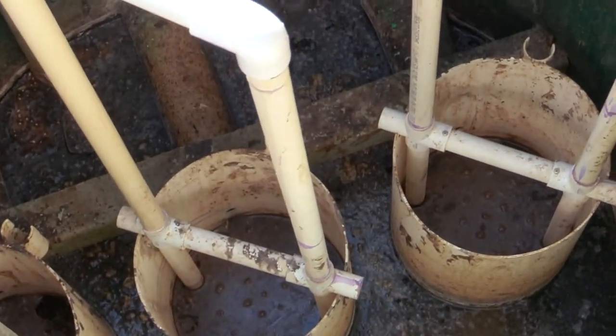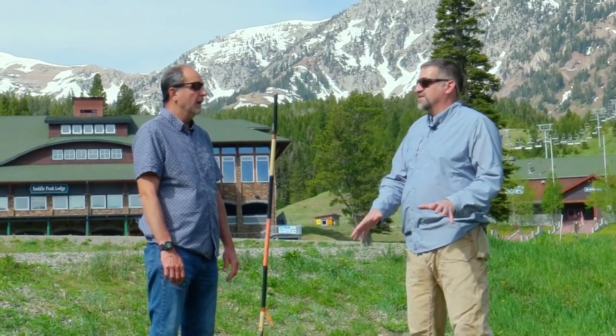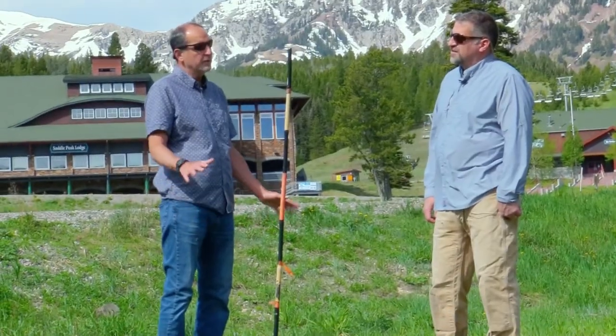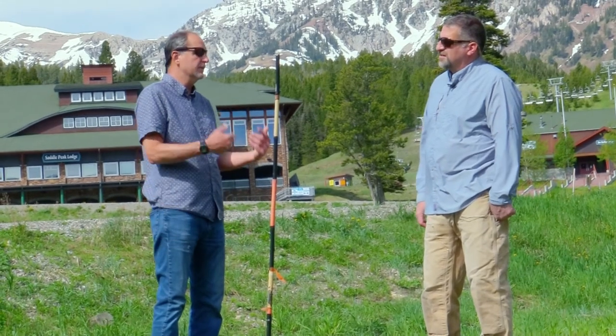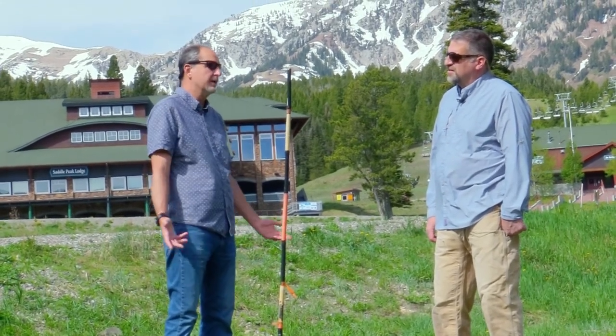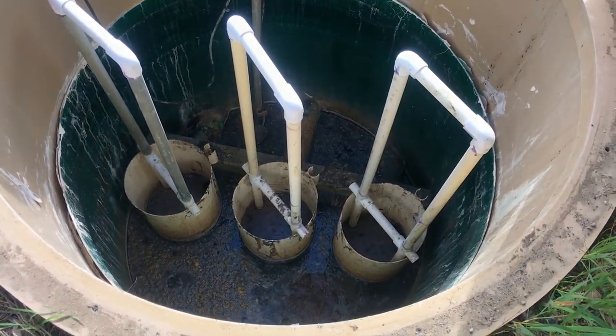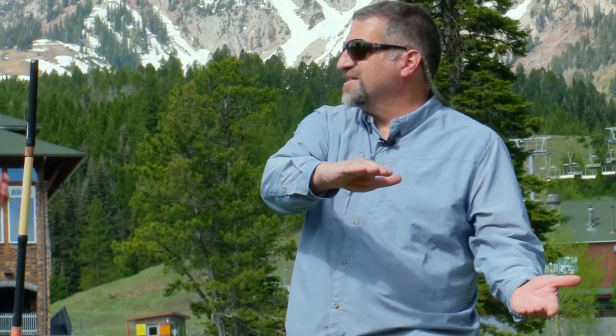Because we're at a ski resort it's cold and there's lots of snow, but this is below the frost line. The wastewater is warm because it's coming out of a building. Typical raw wastewater even in a municipal system is almost equal to groundwater temperature — about 50 degrees. So the septage, the solids sink to the bottom, the floating solids go to the top, the effluent goes out to the next stage. What's left behind gets pumped out by big pumper trucks and disposed of properly.